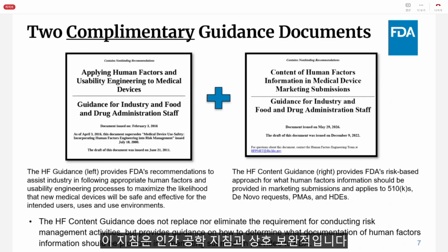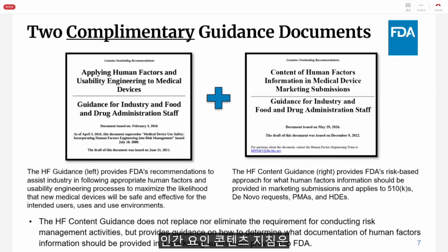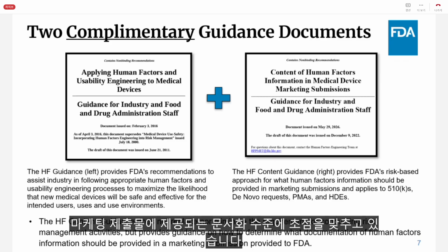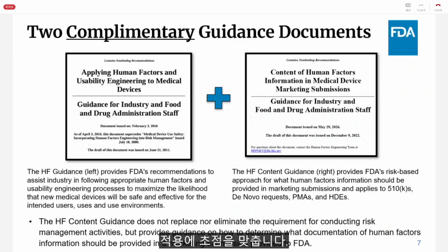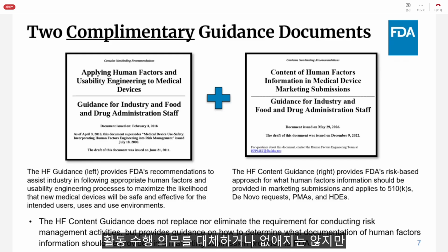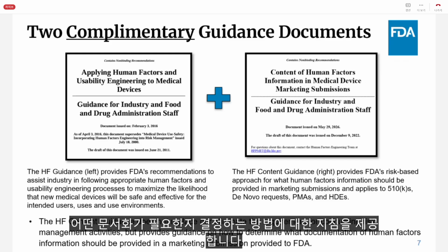The new Human Factors Content Guidance focuses on the level of documentation provided in marketing submissions, while the Human Factors Guidance focuses on the application of human factors principles during the device development process. The Human Factors Content Guidance does not replace nor eliminate the requirement for conducting risk management activities, but provides guidance on how to determine what documentation of human factors processes should be included in a marketing submission provided to FDA.